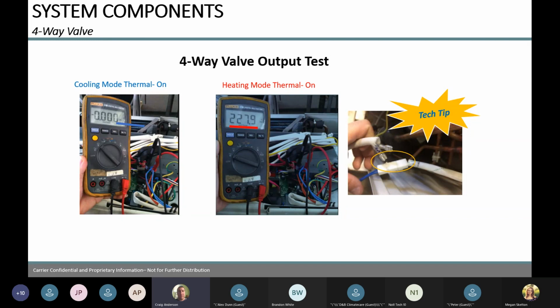To check the reversing valve to see if it's operating, you could put a little magnet on the side of the reversing valve and energize it. Then you would see that magnet slide back to where the copper is in the reversing valve. YouTube is the greatest thing out there for a service guy. Get on there, Google things. It shows you how to put a magnet on it to see if the reversing valve is opening or if it's sticking. You could think it's opening all the way, but it's not. Putting a little magnet on the side of it and energizing it, you'll actually see that magnet slide. It's pretty neat and simple to do, to check whether it's moving or not.